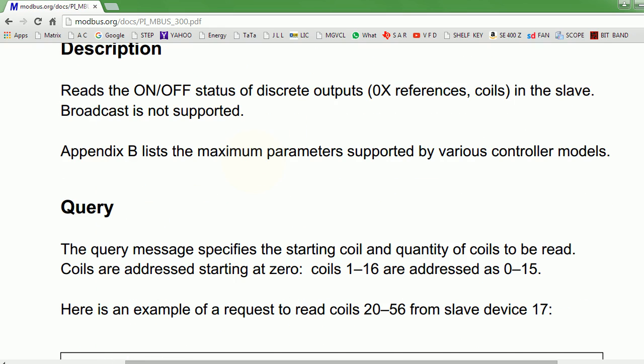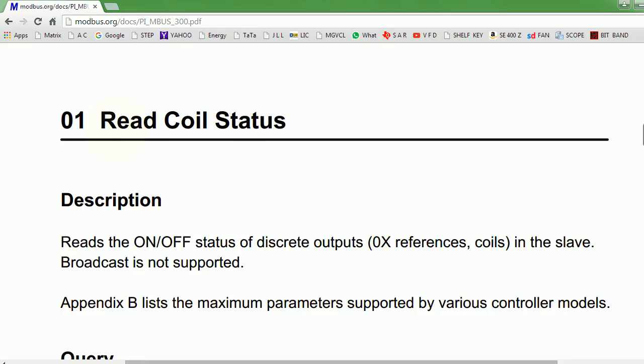We will really be writing drivers for function hex 01. Function hex 01 from a master to a slave means you're trying to read coil status. That means there's a bit which is a memory address inside your PLC, which you have already programmed, your PLC is running, and you want to read the value of that particular bit. Since this is coil, this is both read and write, this has to be an output bit.